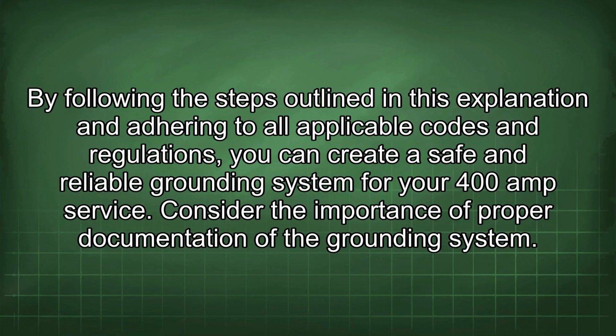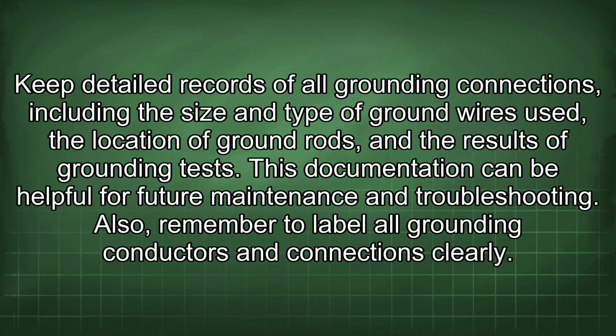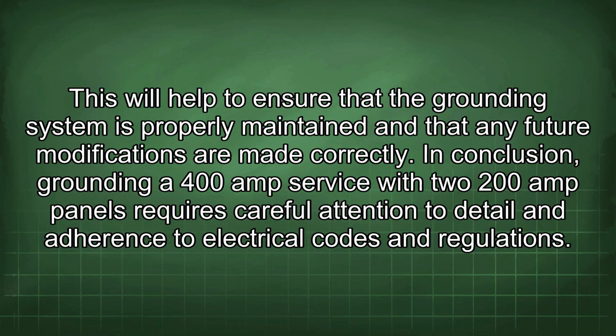Consider the importance of proper documentation of the grounding system. Keep detailed records of all grounding connections, including the size and type of ground wires used, the location of ground rods, and the results of grounding tests. This documentation can be helpful for future maintenance and troubleshooting. Also, remember to label all grounding conductors and connections clearly. This will help to ensure that the grounding system is properly maintained and that any future modifications are made correctly.